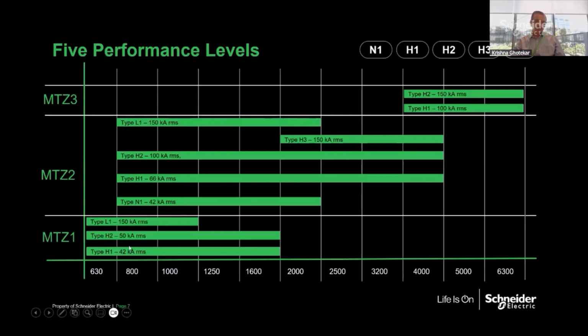So in size 1, you have 42K, 50K and 150K. Next year, in the first half, we will also add a 66K breaker in size 1. In size 2, it starts with 42K, 66K, 100K and 150 kiloampere. Whereas size 3, which is more than 4000 ampere breaker, is 100 kiloampere and 150 kiloampere performance level. So there are some performance levels higher compared to NT and W, but more or less exactly the same performances which today we are delivering to the market.